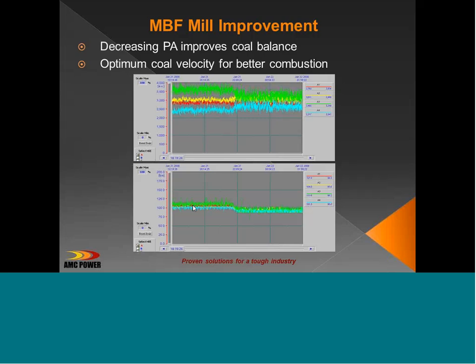It had a slagging furnace. When you opened observation doors, you couldn't even see flames. It was so smoky. When we walked into the control room, we saw the high velocity. We asked the operator to decrease the primary air, and at this point you can see that the velocity of the coal particles decreased with the decreasing primary air.